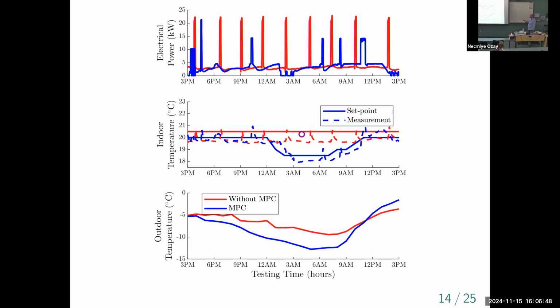The spikes up here in the electric power going up to 24 kilowatts. Does anybody want to guess what those are? Your thermostat switching between. It's not thermostat switching. That's a good guess. It's not EV charging or something like that. It's another good guess. So what this is, is the backup electric resistance heat turning on in this weirdly periodic fashion.